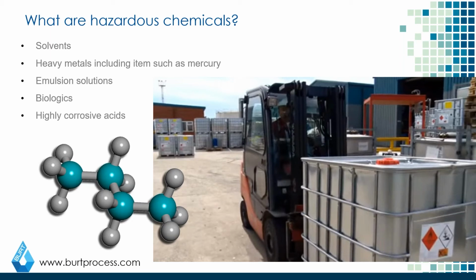These do have environmental controls, obviously, because they generally are located outside. They also have special venting requirements, particularly if you're dealing with a hazardous chemical, which could be Class 1, Div 1, or Class 1, Div 2, as well as some of them also having fire protection based systems as well.